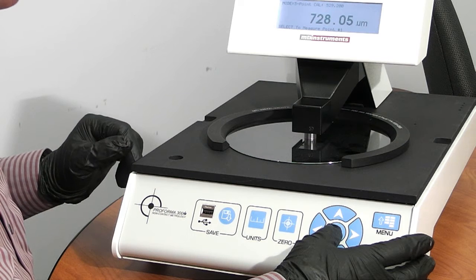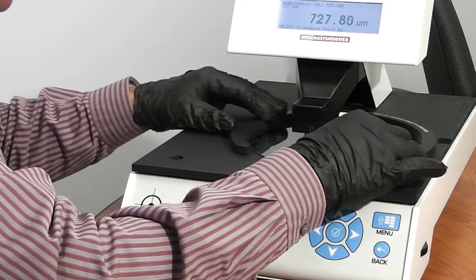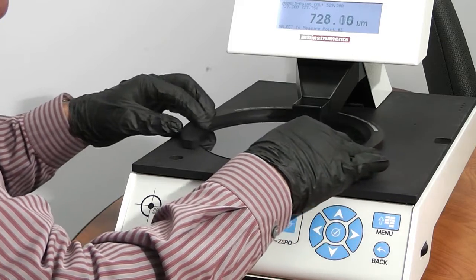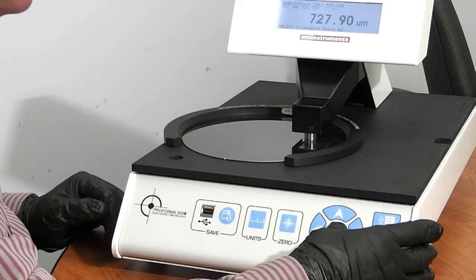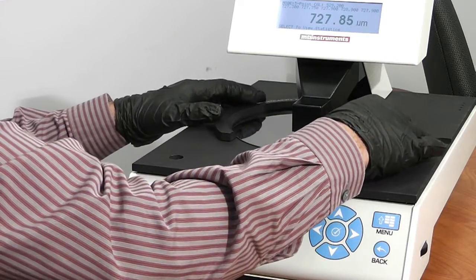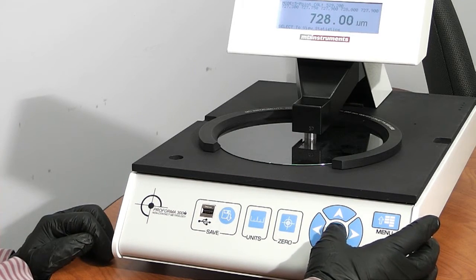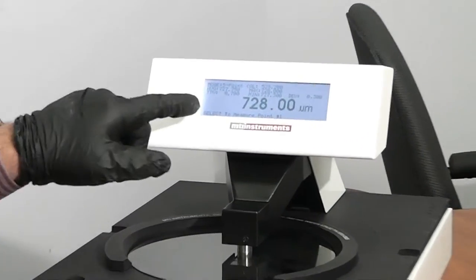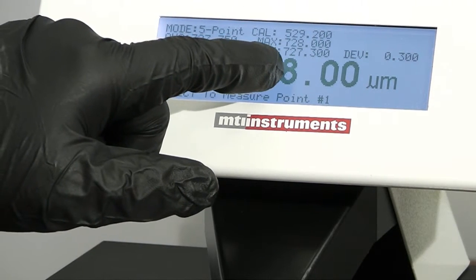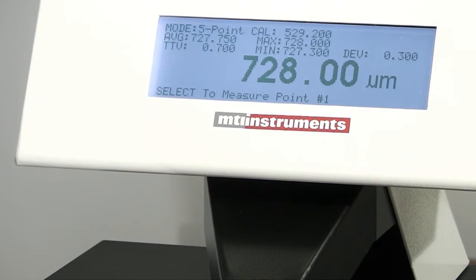So I'm on the first point right now, so we just hit select to measure it. All right, now we're going to go to point two. Let's go over here. Now we go to point three, which is over here. Point four. Make it down there. Okay, next we select to view statistics. So we can see our total thickness variation was .7 microns. We see our minimum, 727, and we also have our maximum, which is 728. Deviation was, standard deviation is .3 microns.